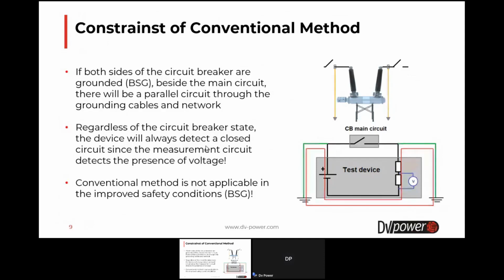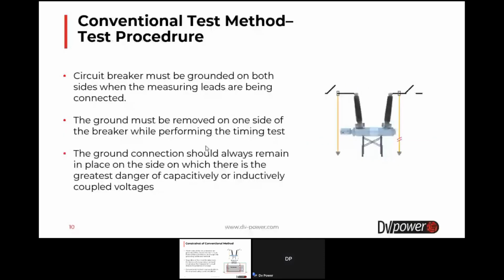The following test procedure should be applied when the test is performed with the conventional method for timing measurement. The circuit breaker must be grounded on both sides when the measuring leads are being connected. The ground must be removed on one side of the breaker while performing the timing test. The ground connection should always remain in place on the side on which there is the greatest danger of capacitively or inductively coupled voltages.